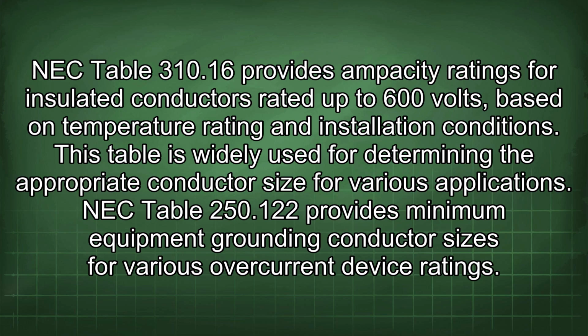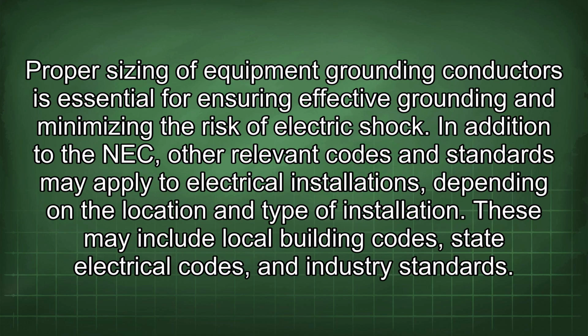NEC Table 250.122 provides minimum equipment grounding conductor sizes for various overcurrent device ratings. Proper sizing of equipment grounding conductors is essential for ensuring effective grounding and minimizing the risk of electric shock.